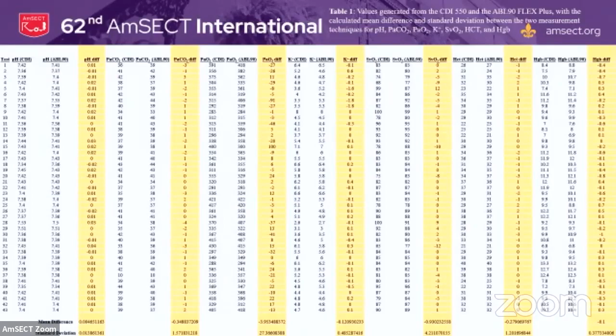So this is a lot, but this is just my raw data. You can see here that the first row is the CDI, then the analyzer, and then the difference. I repeated that for all the parameters, and I took an average at the bottom. That would be the mean difference. And from there, I could compare it to the published accuracy limits in the manual. So for instance, the first one, 0.007, the CDI read 0.07 higher. For mine, can't quite see it, but it wasn't that much.